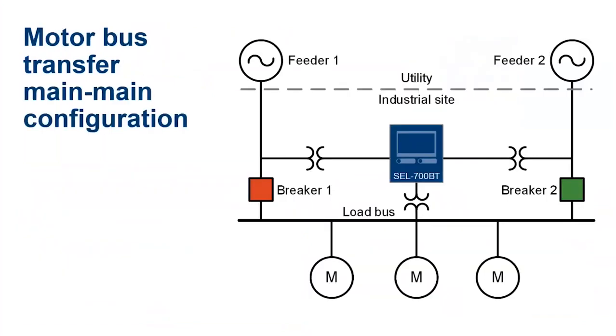Okay, so there are two main configurations that we support. One is the main-main, and that's one relay connected. So we have 3 voltages on feeder 1, 3 voltages on feeder 2, and then 1 voltage on the bus. And those can be in any combination of line to neutral or Y or delta connected PTs or single.